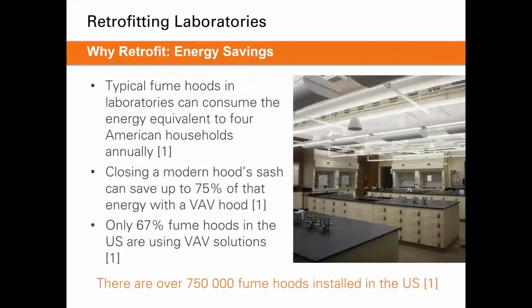So you can tell from that description that constant volume hoods may not be the most efficient option and can actually be very inefficient. They do make sense in certain cases. Those cases are when the lab is thermally driven or ventilation driven, meaning that the supply is the one determining the air change rate. In labs where the fume hoods are governing that air change rate, so they're fume hood driven, then it makes sense to go with a VAV hood, because if the hood is not in use, you can turn it down and that won't inflate your supply any more than it needs to be, and then it can go into a state where it's doing thermal control. So CV hoods do make sense in those specific cases because they do have a cheaper upfront cost, but in most cases where the labs are fume hood driven, a VAV hood is what you want to go with. Otherwise, you're going to be having a lot of excess ventilation in those spaces.